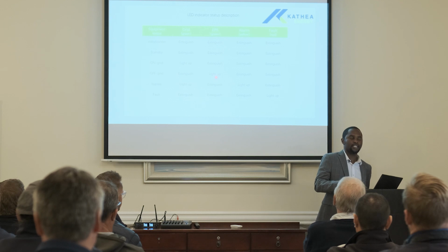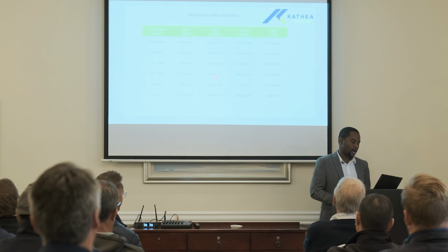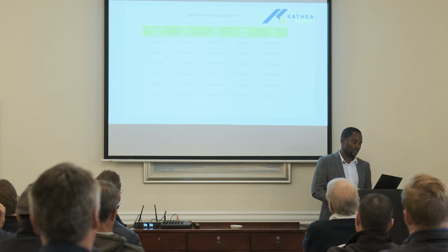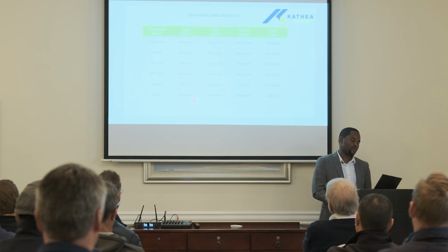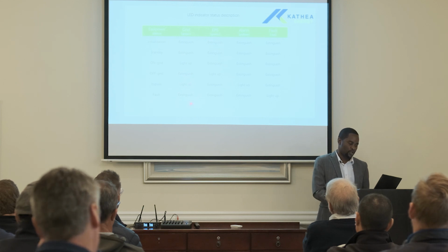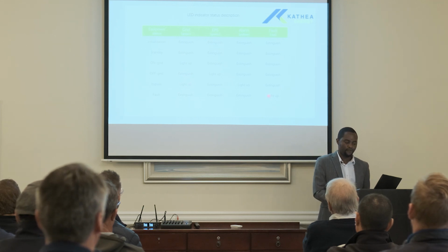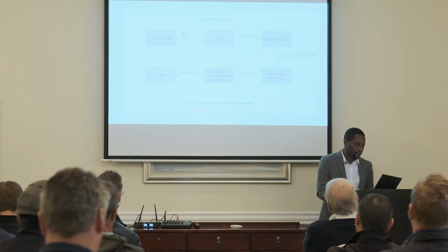You might face challenges when you lose grid for me to switch over to backup. But the normal scenario is when your EPS, your grid is on, or your EPS is on, like in this off-grid mode, or your EPS and your grid are on, you know you are sorted. Then the fault: you can have a fault alarm on the fault LED, then you need to attend to this before your inverter can work.